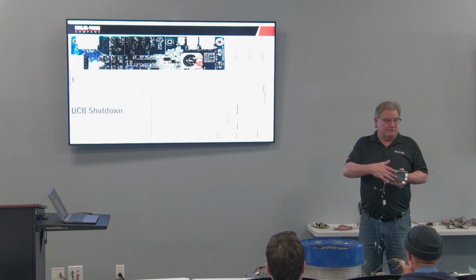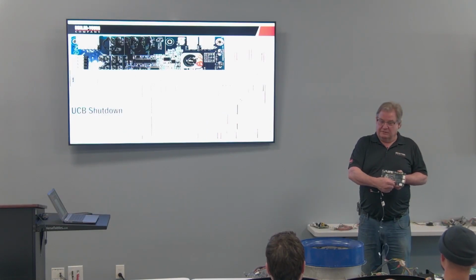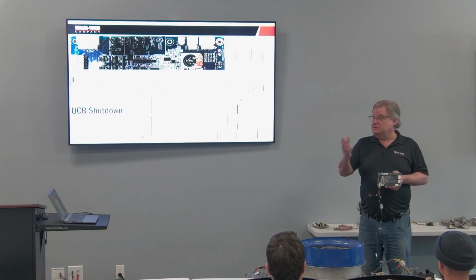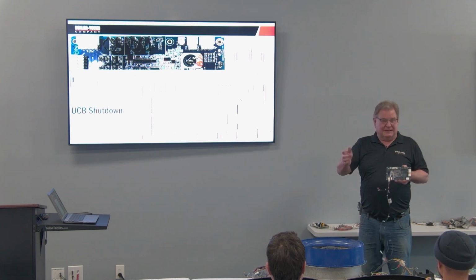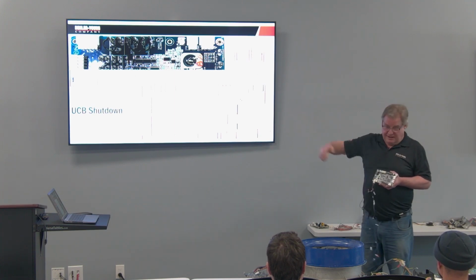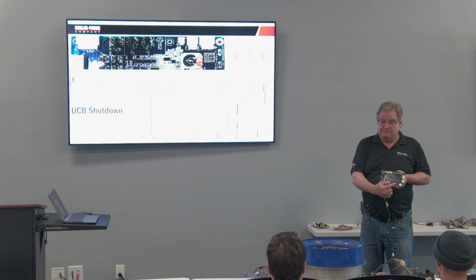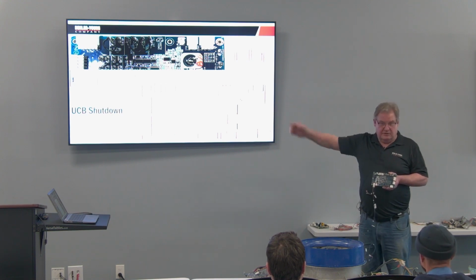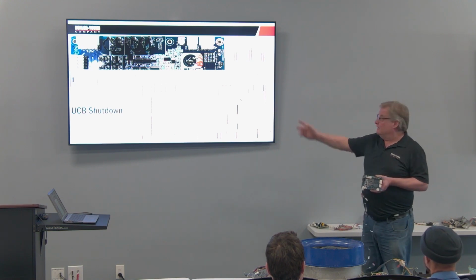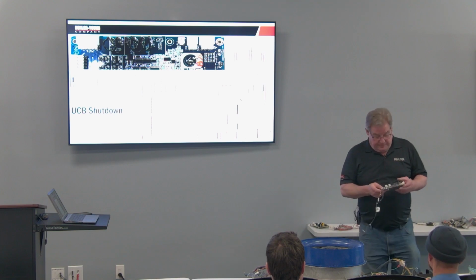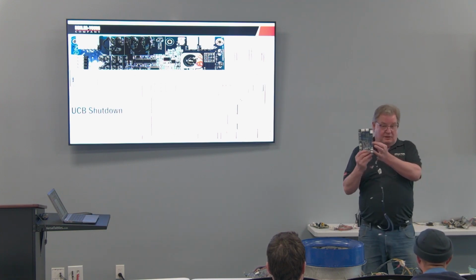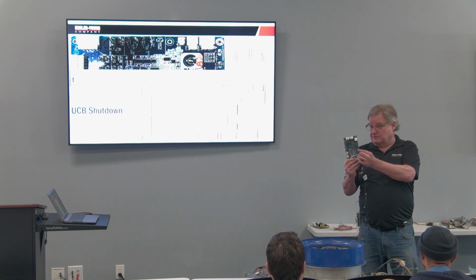Okay, so it's important you know how this works, because we get lots of calls on that. I'm losing 24 volts. Well, if we see how the flow goes, because I've got nothing at R and C, so these jumpers, the safety switch, then to R. Okay, it's right there. And again, if you're doing a smoke detector, make sure you go to the 24 out to power the smoke detector.